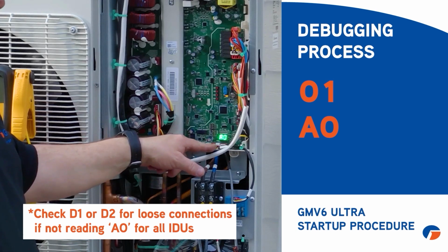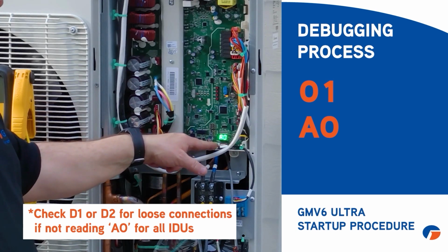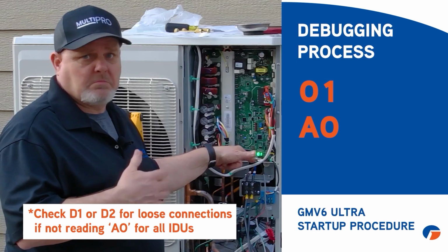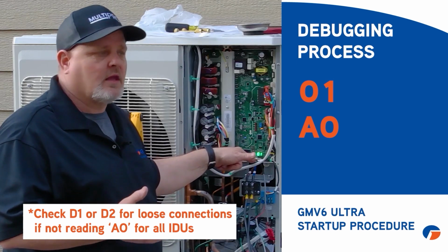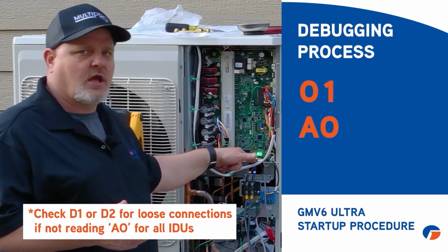And you may need to go back and double check your D1 and D2 communication wiring to make sure we don't have a loose connection, or we missed hooking up a head, or whatever it may be. Because all of those indoor units should say AO.